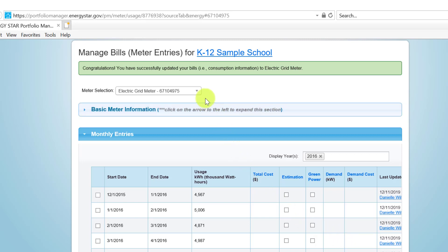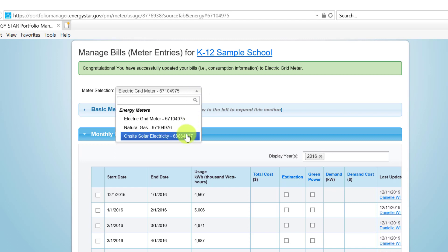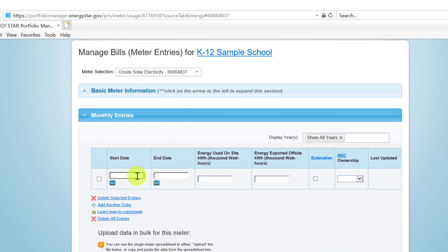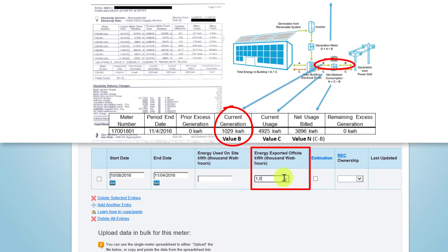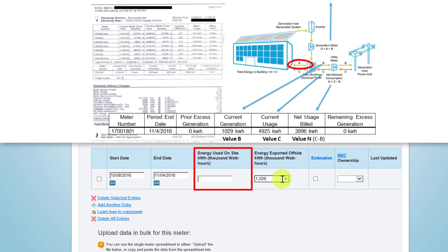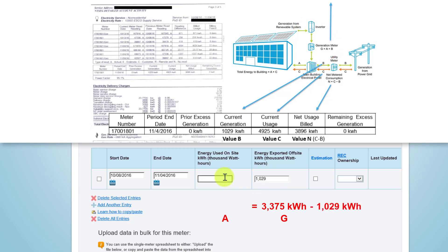Next, we need to account for the energy consumption associated with our on-site renewable energy generation. To do this, you can select that meter from the drop-down list on the Manage Bills page, or if you've already returned to the Energy Bills tab, simply click on the meter name. First, define the date range for this meter entry — this should align with the period you previously entered for the grid electricity meter. From the utility bill, we know that current generation is equivalent to Flow B on the Energy Star diagram. This value should be entered in the field labeled Energy exported off-site. To obtain energy used on-site, or Flow A, we need to do some quick math: this value will be equivalent to the total on-site renewable energy generation for the period, value G, which should be available via the on-site solar photovoltaic system, minus the energy exported off-site, or Flow B. In our case, this is 2,346 kWh.